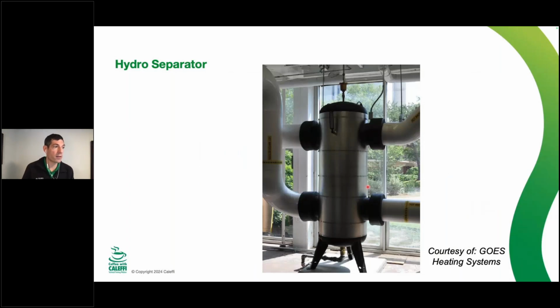This is a chilled water scenario. So you can absolutely use these hydro separators for chilled water. You just have to insulate it really well, as you would for anything else. What changes is you actually kind of flip the piping upside down. So the hot water is always on the top, which in a chiller scenario would be the return instead of the supply.